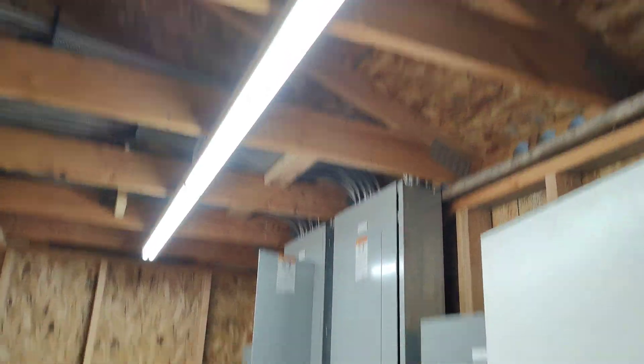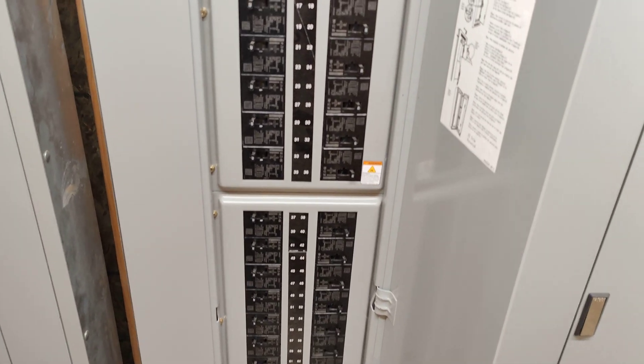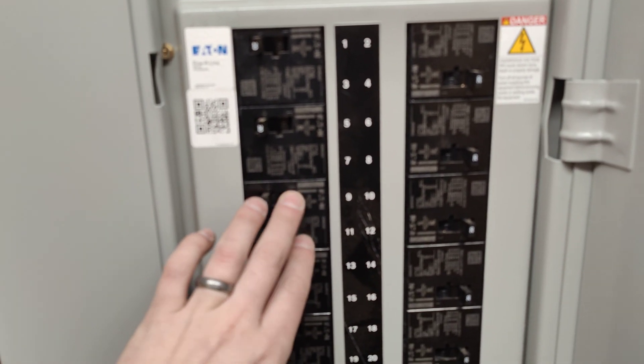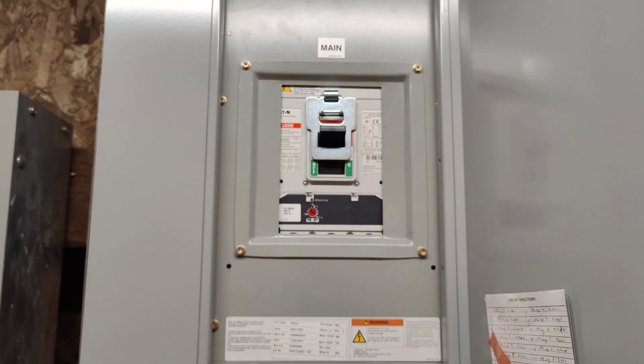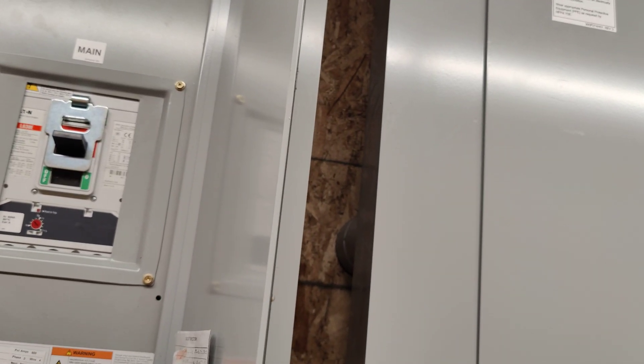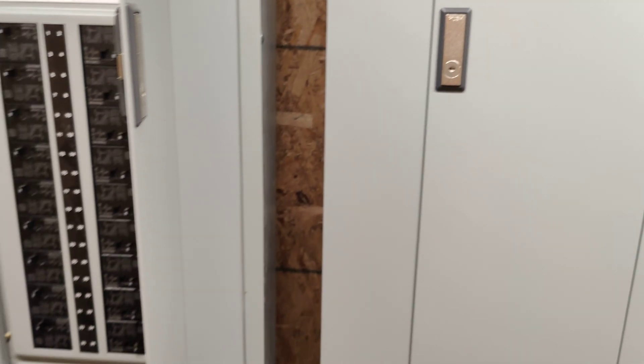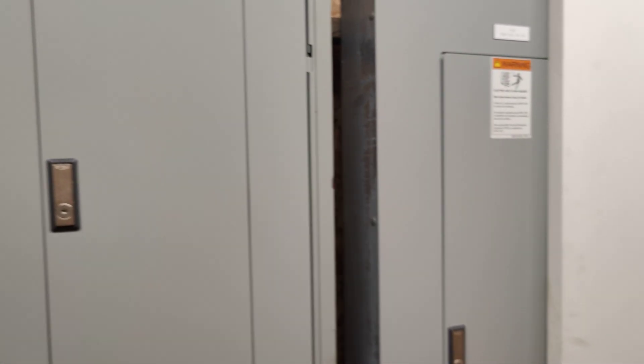This room is the room with all the panels. Again, it's a 300 kVA transformer. You can see our 20-amp breakers here going all the way down. And then you've got your main breaker for this designation — P2A, P1A, P1B. So I think this is a 600-amp panel. I think these two are in one line and it's 600 amps. And then you have this one over here — I don't know exactly how much that is, probably 400 amps.